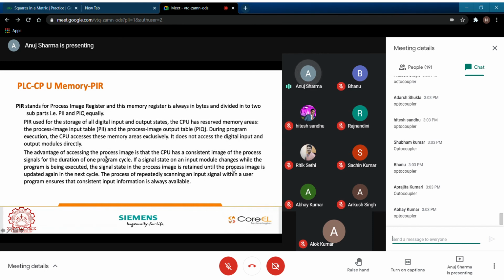The advantage of accessing the process image is that the CPU has a consistent image of process signals for the duration of one program cycle. If a signal state in an output module changes, or when a signal state of an input module changes while the program is executing, the signal state in the process image is retained. So PII and PIQ retain that particular signal in memory until that cycle of operation completes, and update it again in the next cycle.